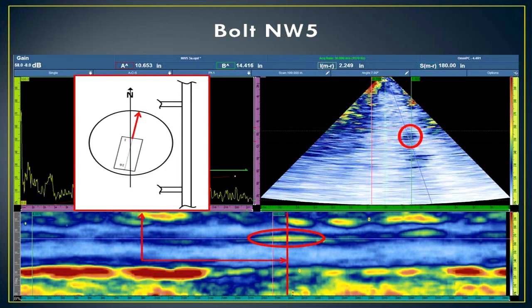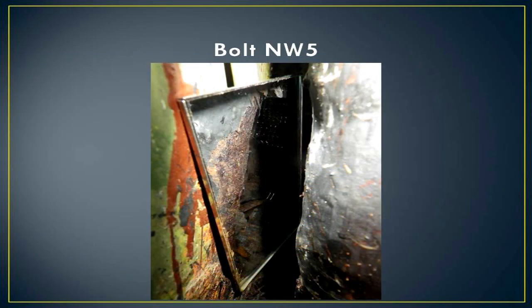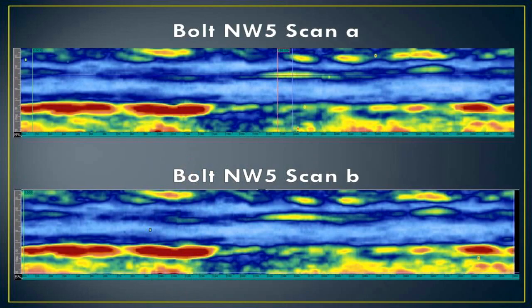Then I rotate my probe over to face close to the north face of the bolt, and got a pretty good indication there on the side, down about 10.5 inches. And if we look at it, I apologize for the quality of the picture. It was hard to get pictures of that stuff around there. You could hardly even fit the mirror in there, but you can tell that there's definitely something going on right in that location.